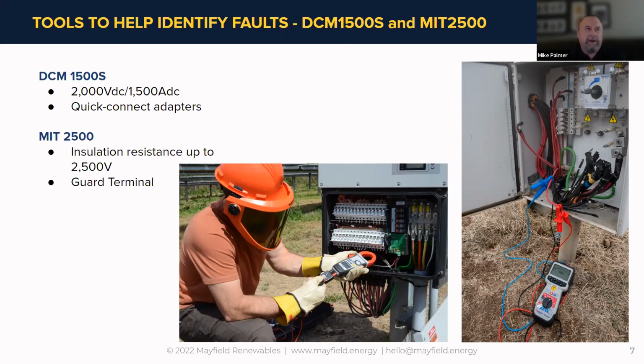But on the side of caution, we always recommend that you check with the manufacturer. And to be honest with you, they've been really good about getting back to you in a timely manner. I can't tell you which ones, we've talked to them all. Typically what I found is about half of them will say, no problem, go forward with the test, and then some of them say, you better be darn careful. And we certainly never want to violate the voltage on our string and on our array. If it's a 1500 volt string, that's what we're testing to.